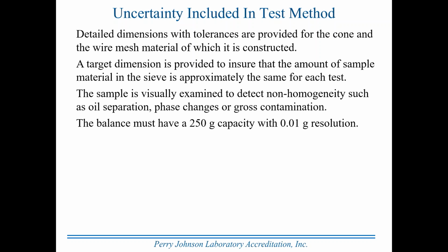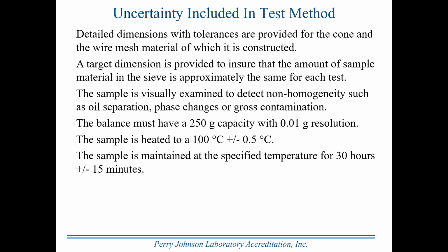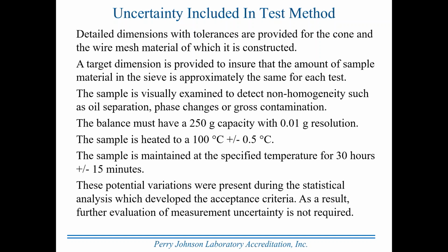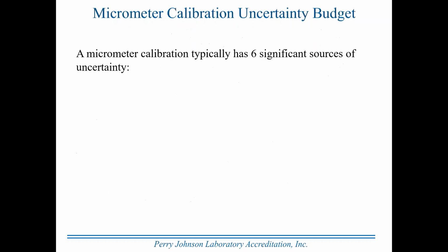The balance must have a 250 gram capacity with 0.01 gram resolution, fairly small resolution. The sample is heated to 100 degrees C plus or minus 0.5 degrees C. Sample is maintained at the specified temperature for 30 hours plus or minus 15 minutes, 15 minutes being a quarter of an hour. These potential variations were present during the statistical analysis which developed the acceptance criteria. As a result, further evaluation of measurement uncertainty is not required.